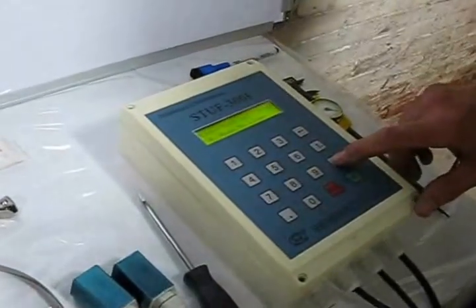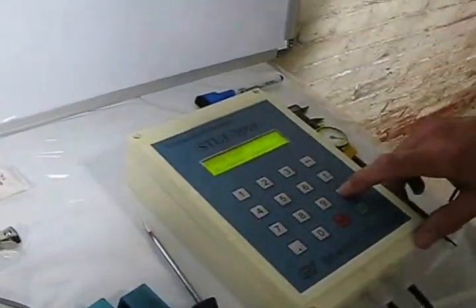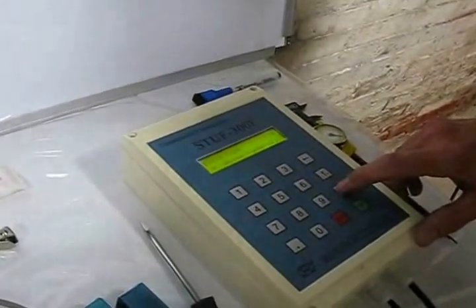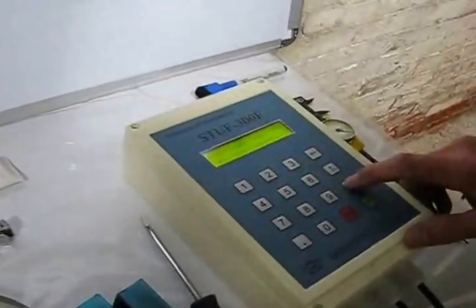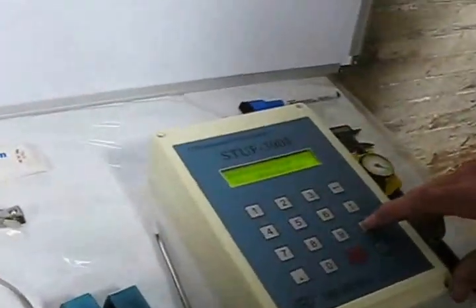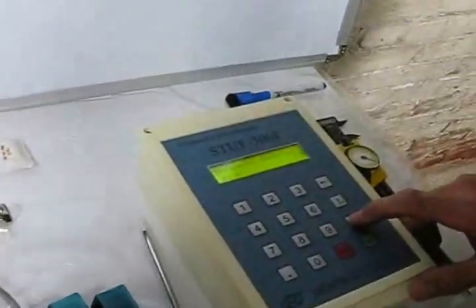There is no liner at this point, so there's no need to enter any dimensions for the liner material. The fluid type is water. This is a water main. We enter water. We enter the transducer type, which is S1. And the installation of the transducer is a V mounting.